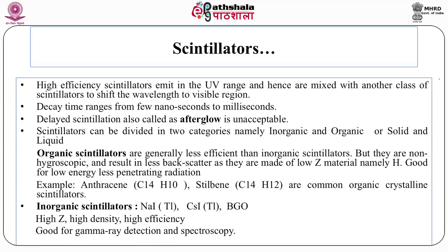Among the most popular inorganic scintillators are sodium iodide activated by thallium, cesium iodide activated by thallium, and bismuth germanate. They are most popular inorganic scintillators. They are high atomic number, high density. As a result, they are high efficiency radiation detectors. In some other module, you will be knowing how high Z material, high atomic number material, high density material are also high efficiency radiation detectors. In this module, we'll restrict ourselves only to the detection part and not discuss the physics of how radiation interacts with matter. So these scintillator detectors are good for gamma ray detection and spectroscopy.